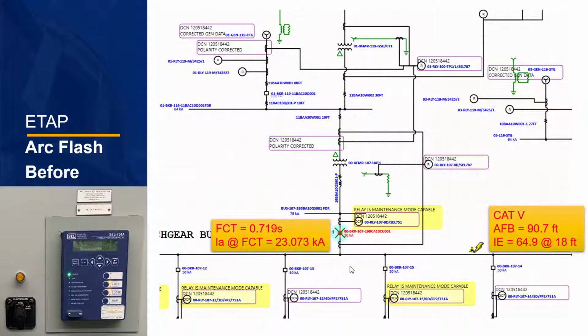In this slide, we see a portion of the protection single line modeled in ETAP and the calculated arc flash incident energies on the medium voltage bus system, in this case 6.9 kV. Arc flash studies are performed using the IEEE 1584 method, and we can see the arc flash boundary is 90 feet. This is due to the fact that the protective devices take up to about 3/4 of a second to clear the fault. This indicates that if a worst case full 3-phase bolted fault were to occur, a person standing within 90 feet of the gear would experience a second-degree burn as a result.